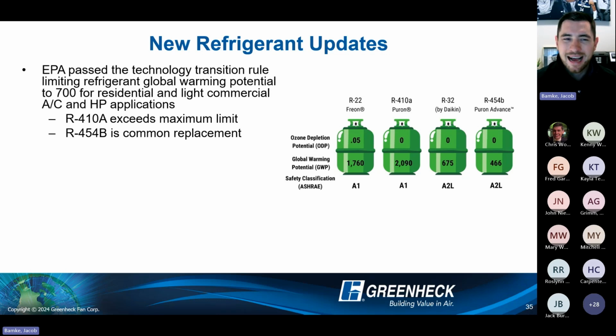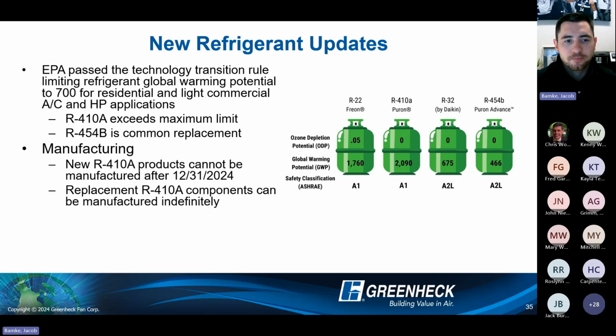And when you look at the common replacement, R454B is what we've seen the most of so far. R32 is certainly going to be a used refrigerant as well. Both of those are under that 700 GWP value. You can see 454B goes a little bit lower. Nonetheless, they both are under that threshold. The other thing to point out in that graphic is the safety classification. So we are moving into A2L safety classification territory, which means a mildly flammable refrigerant. So there are additional safety requirements that come with it, which we will discuss throughout.